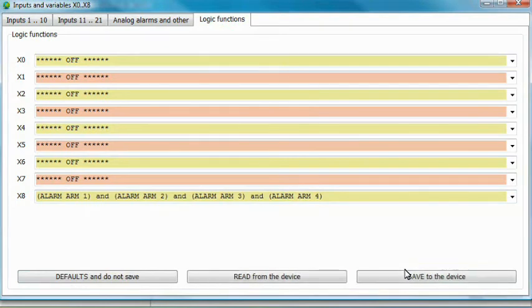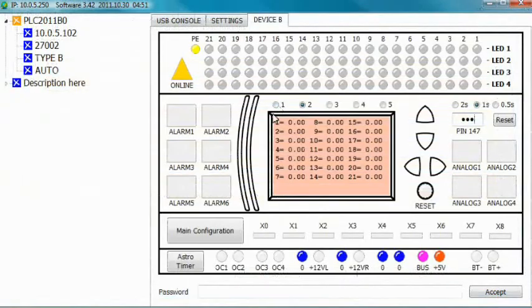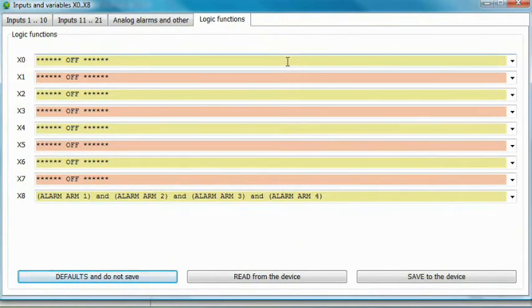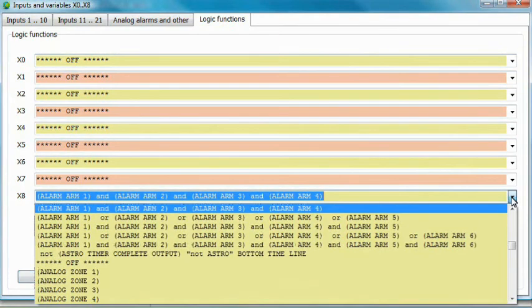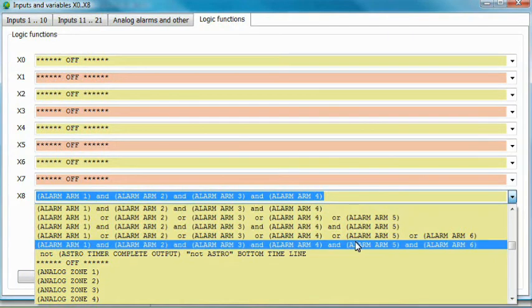Again, save the configuration and check if it works. As you can see, the variable is only active when all 4 zones are armed. You can later direct that variable or group of variables, depending on what settings you have made, to an output or to carry out other functions. Other configuration options include activation of the variable when an alarm is triggered, activation of the variable when an analog zone is triggered, or armed.